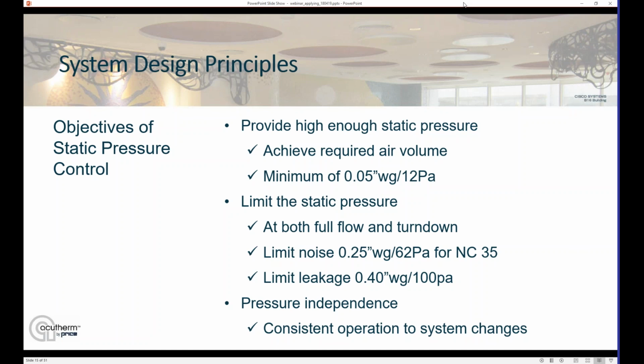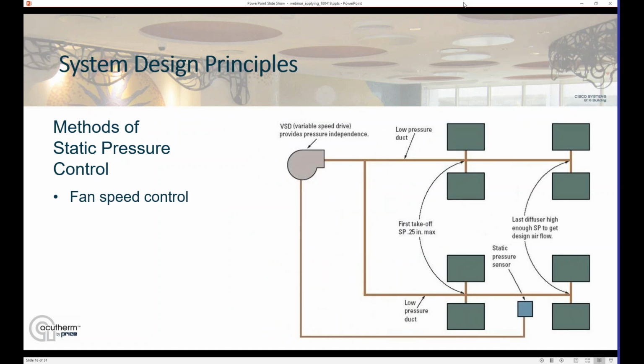The diffusers themselves are pressure-dependent devices, so we have to design this into the system supplying the diffusers. One of the best ways to do this, and when I say best, meaning the lowest energy method, is with an all-low pressure system and fan speed control. In this approach, the static pressure at the diffuser furthest from the fan is high enough to achieve our design air volumes. The duct design is such that the static pressure at the diffuser closest to the fan is no higher than 0.25 inches water gauge.